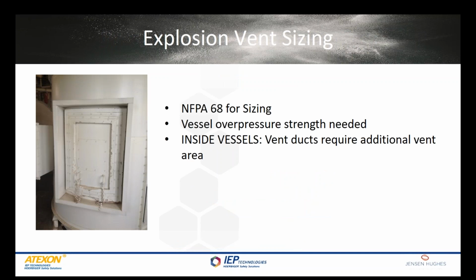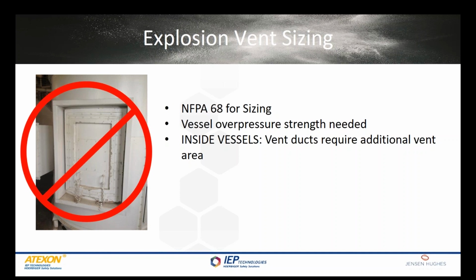NFPA 68 is the standard that we use primarily throughout North America for sizing of explosion vents. NFPA does allow the use of vent ducting to the outside if you have an inside vessel. So if you have a vessel that's near an outside wall, you can indeed put an explosion vent on that vessel and duct it to the outside.